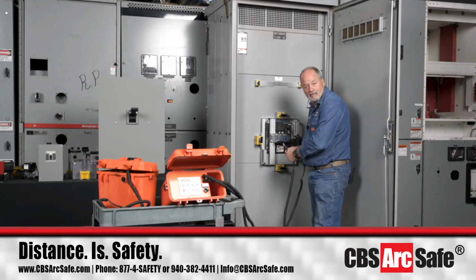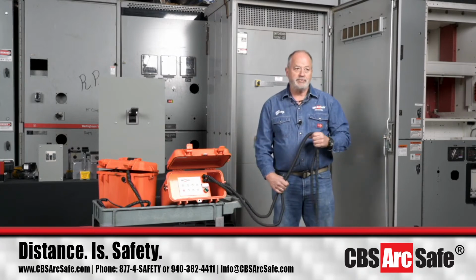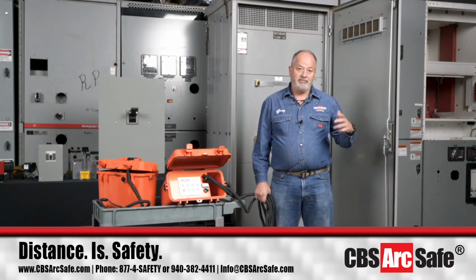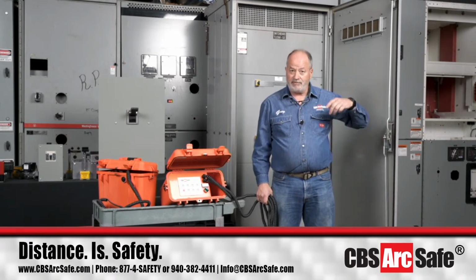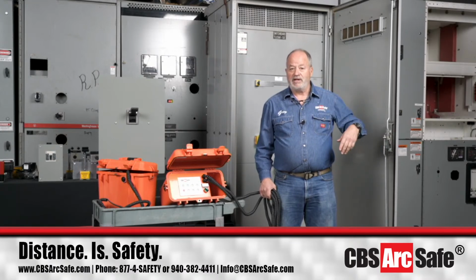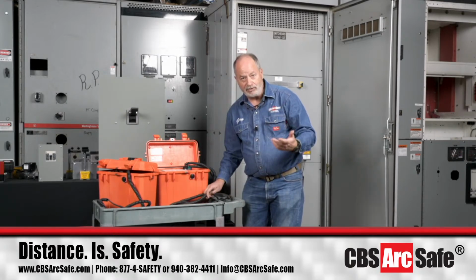Greg, we had another question on T1 and T2 times. They're asking, are T1 and T2 times adjustable, or are they breaker specific? They are breaker specific for the most part. We do a lot of testing to figure this out before we market or sell a product. We play with various amp frame sizes to make sure it's not going to change as we go up in frame size, going from an 800 up to a 5,000 amp breaker. If it changes at all, we post the changes and say, okay, it's good for 800 through 3,000 amps, but 4,000 to 5,000 is different because you've got bigger springs or something, and we annotate that with the RSA based on what it has to be able to do.